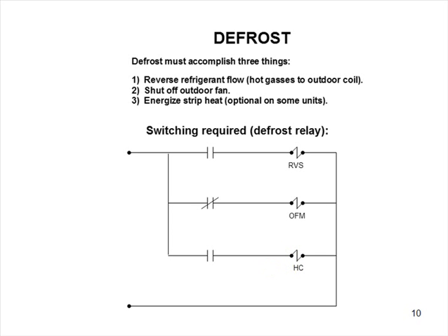Back in the 70s, 75, 80, I was working for a wholesaler at the time. When you bought a heat pump from a major brand, you had to buy a separate kit that would bring the strip heat on in defrost mode. The reason they did that, they tried to pull a slicky. They thought if they didn't energize the strip heat during the defrost cycle, and they submitted that to ARI as their test results, then their COP and the HSPF would be higher, because this amount of energy never came into play. It was an option you had to buy, and the contractor had to plug it into the circuit board.